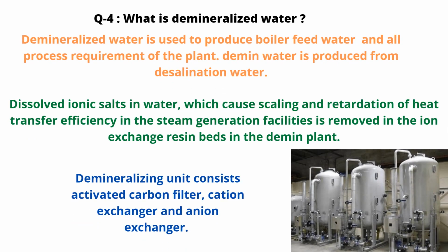What is demineralized water? Demineralized water is used to produce boiler feed water and for all process requirements of the plant. Demin water is produced from desalinated water. Dissolved ionic salt in water, which causes scaling and retardation of heat transfer efficiency in the steam generation facilities, is removed in the ion exchange resin beds in the Demin plant. The demineralization unit consists of an activated carbon filter, cation exchanger and anion exchanger.